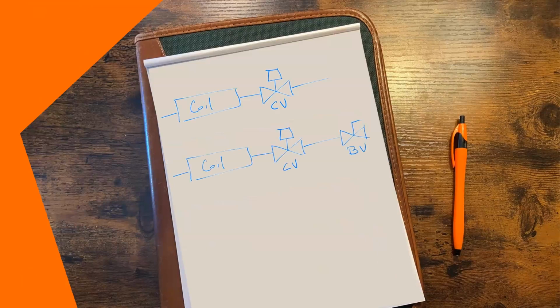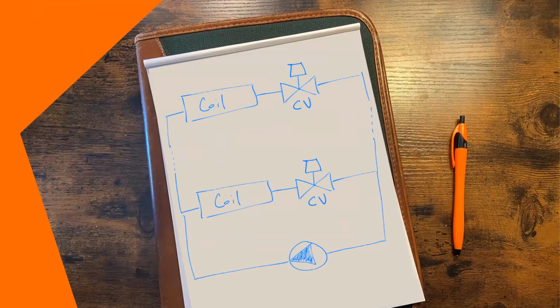So here we're going to discuss three possible ways we could pipe the control valve that we selected with a coil. The first is a coil or a branch that has no balancing device. The second is going to be with a manual balancing valve. And the third one is going to be with an automatic balancing valve or an automatic circuit setter or flow limiting valve. So let's say we have a simple direct return piping system. In this configuration, we have higher pressure drops across the branches that are closest to the pump and lower pressure drops further away, as shown here.